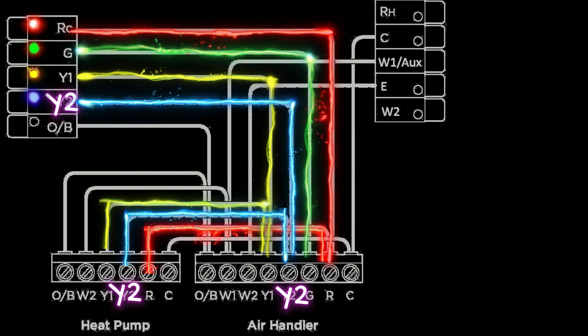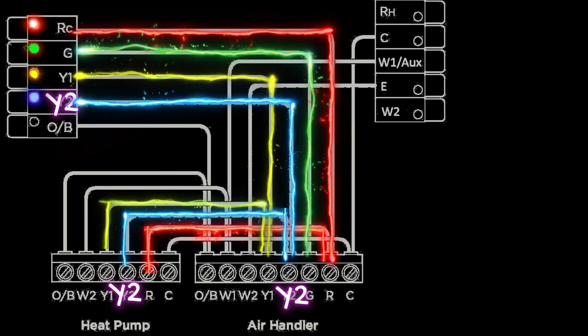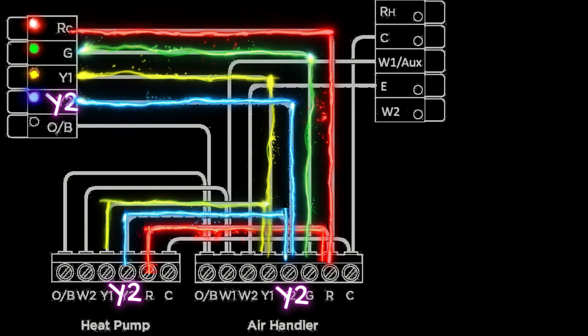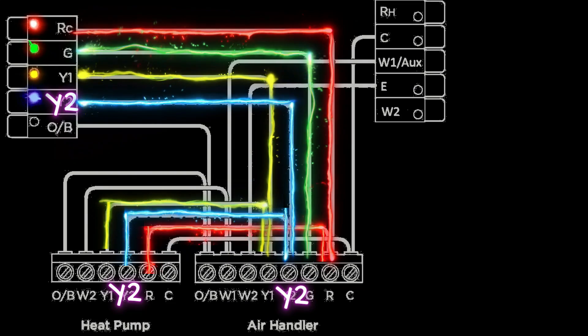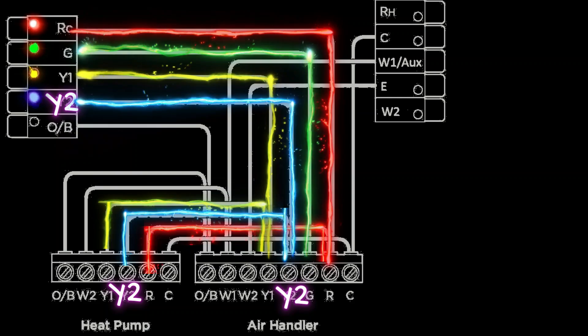Now some units have two compressors, one for each stage. Some units have a single compressor that's staged by itself. So this Y2 signal is going to either initiate a second compressor or initiate a second stage in a single compressor. If you have a variable speed condenser fan motor, this will also initiate a higher speed on that motor.